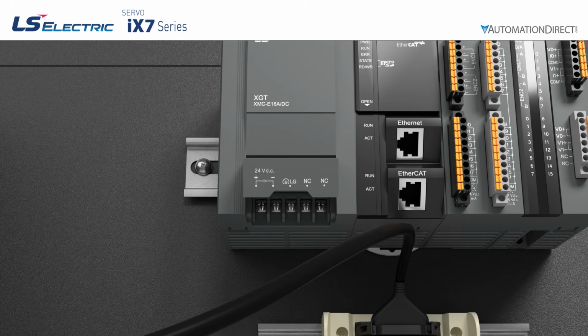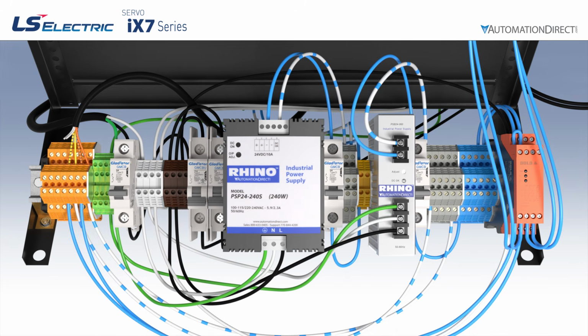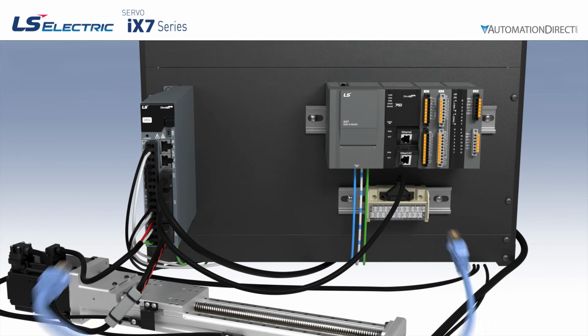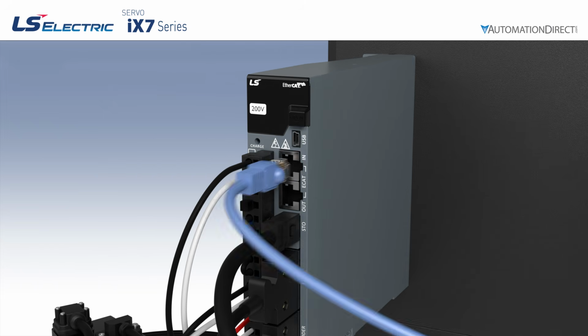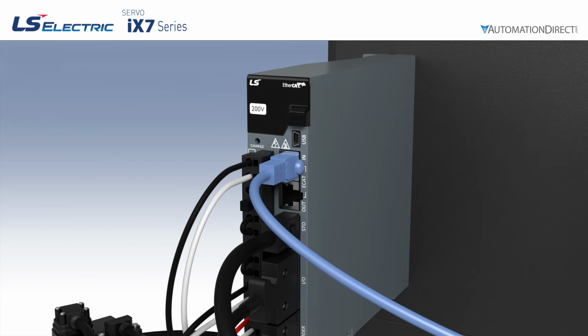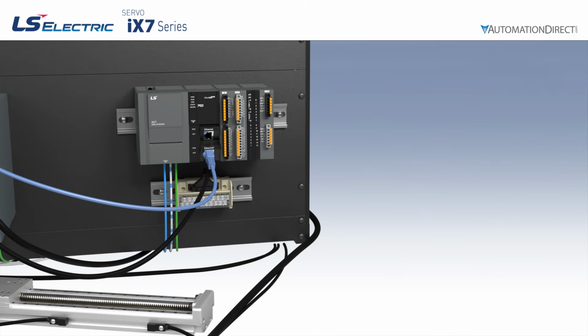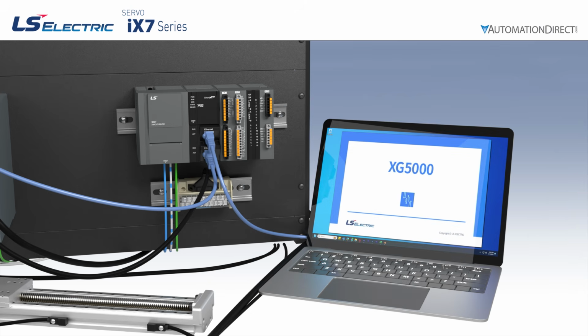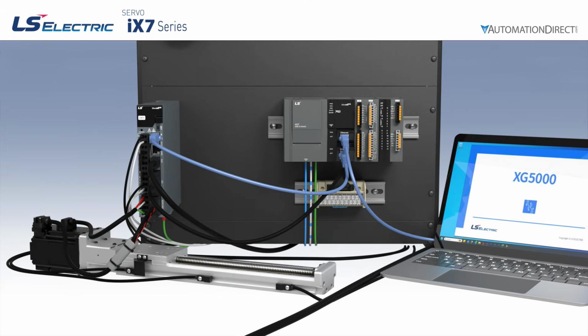Power for the XMC controller can be 24-volt DC or 110 to 240-volt AC, depending on the model. Ours is a 24-volt DC model, so we'll power it from our controller power supply and connect the controller ground. For communications, connect an Ethernet cable from the controller's EtherCAT port to the drive's EtherCAT in port. It will not work if you connect the controller to the drive's EtherCAT out port. Connect another Ethernet cable from the programming computer to the controller's Ethernet port. And finally, connect a USB cable from the computer to the drive, so we can configure the drive and program the controller at the same time.